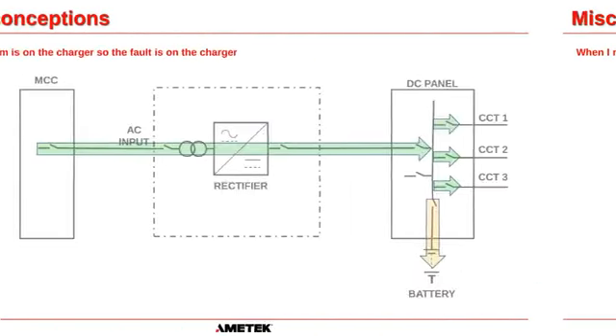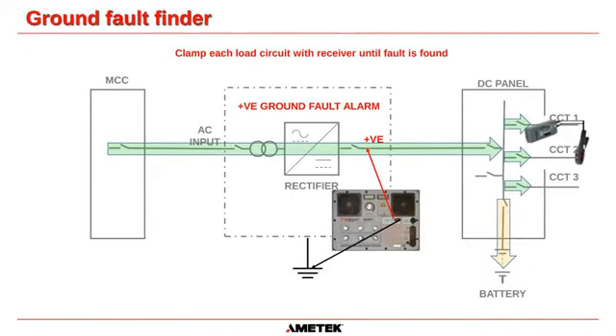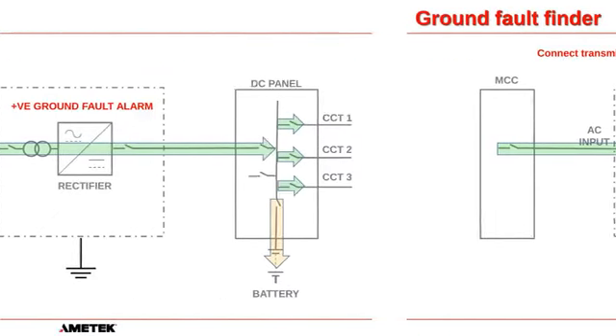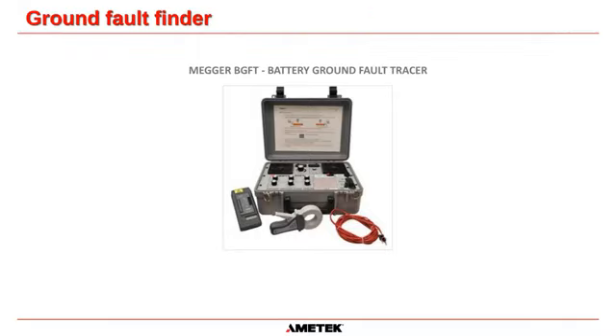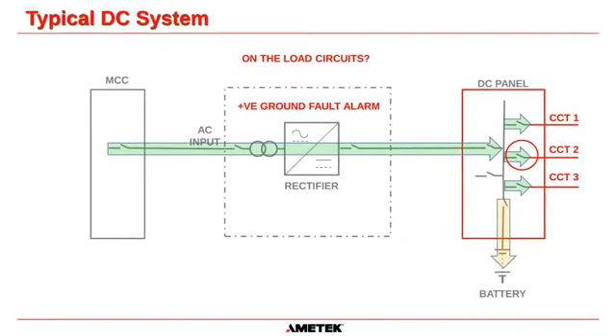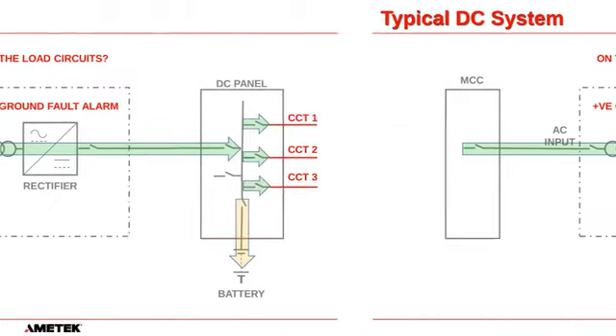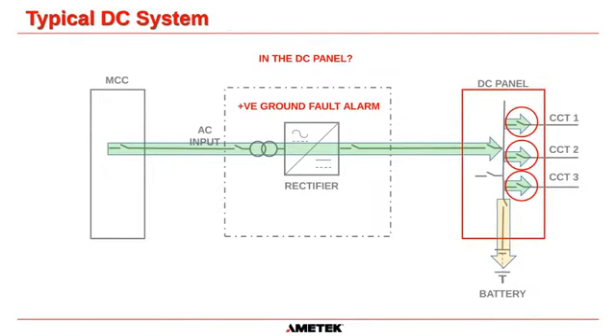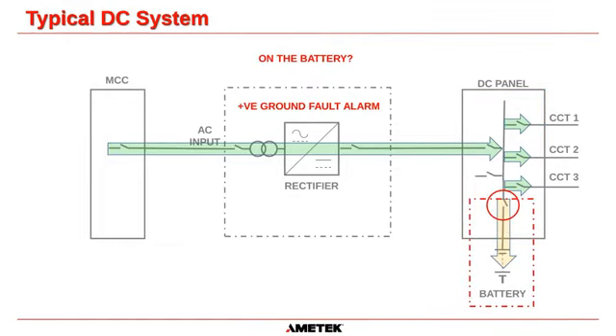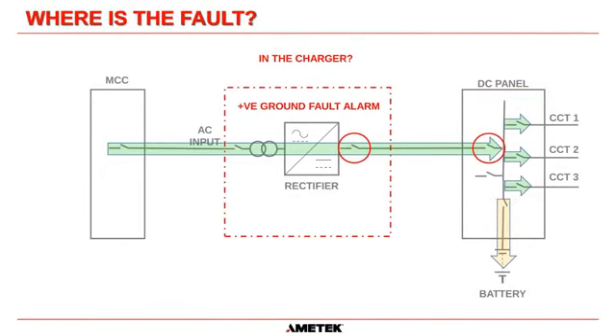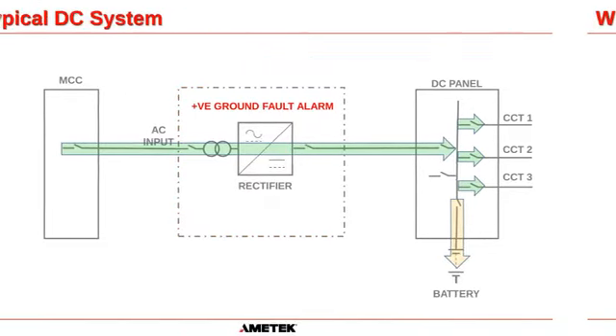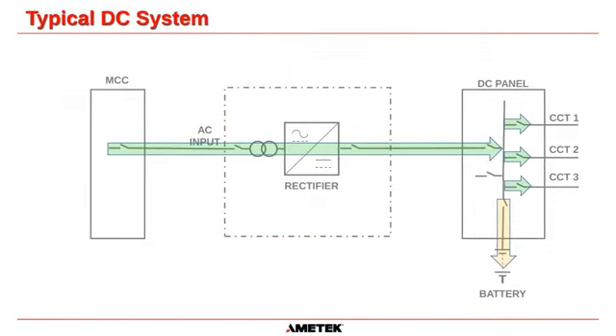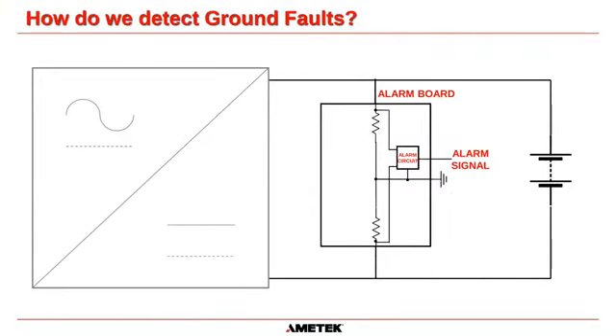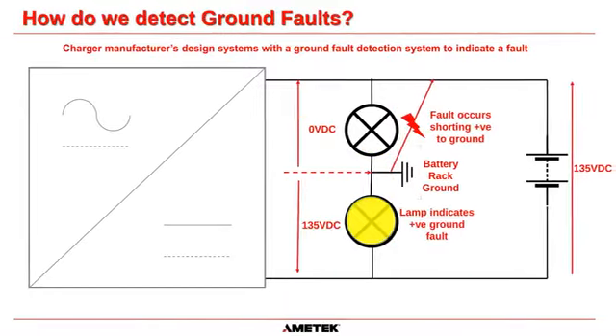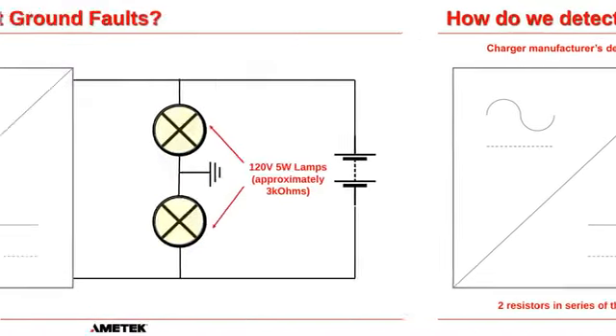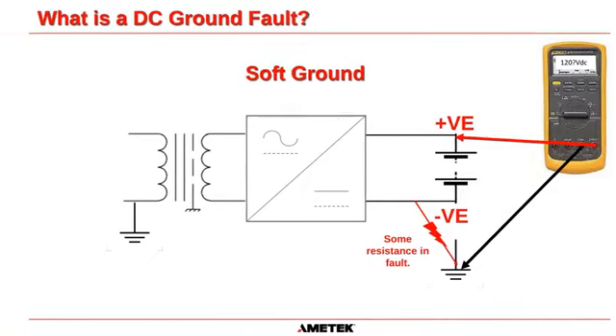I know we're running late, guys, and if you've had to log off, I completely understand. But this is very important, and there are so many commercial style UPSs out there, especially older ones that don't have isolation transformers in them, that consistently shock battery technicians all the time. I've been shocked by one of them right at the start of my career, and I wondered what the heck happened. And it is down to not having an isolation transformer. So let's go back. Sorry, the way that this program works, I can't select the slide and go back.